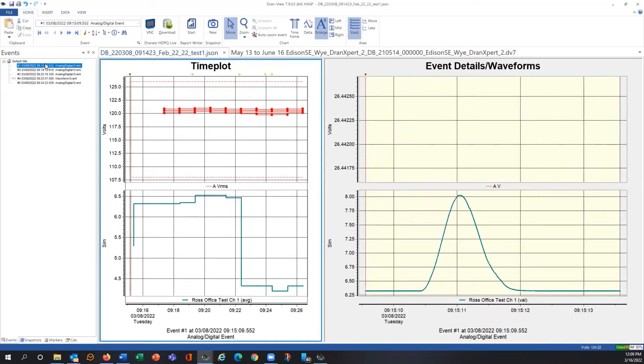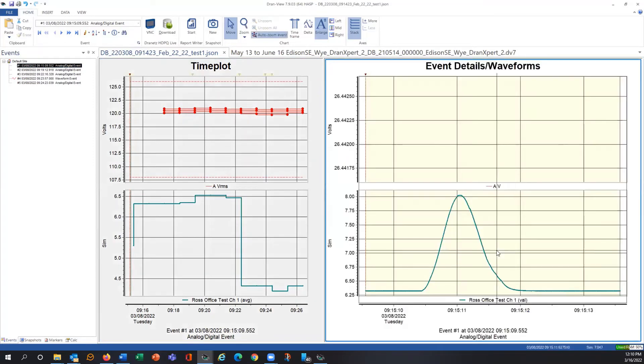This is simply done by adjusting that knob you saw on the demonstration system. I turned it up — the high limit was at six and a half volts — so you can see it triggered at this point. Here's the post trigger as I brought the knob up and then back down again. This would be the same for a temperature input: as the temperature transducer goes up and down within high and low limits, you could alarm on it in DRAN expert — useful for a data center where you need to know when chillers aren't working.